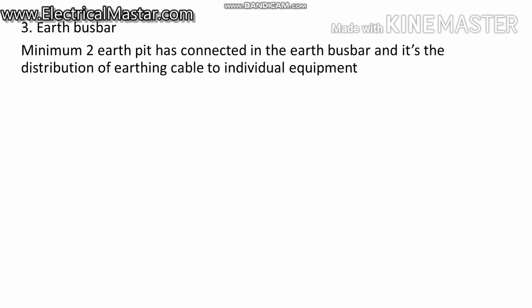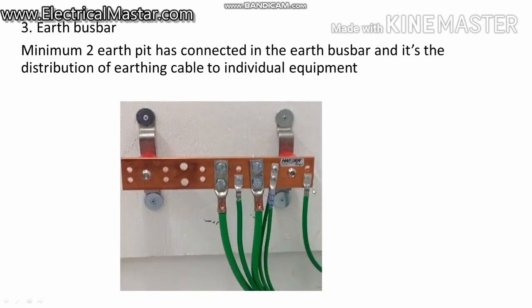And third, the earth bus bar. We can say the earth bus bar is the hub of the earthing connection. From the earth pit we give the input cable to this earth bus bar. This earth bus bar acts like a DB, a distribution board, an earthing distribution board. From this earth bus bar we take the output to the individual equipment. See here, these are the individual cables and two big size earthing connections. They are the incomers of the earth bus bar. As per the standard, you have to provide a minimum of two incomers, two earth pit connection inputs to this earth bus bar. And the output is based on the number of holes present in the bus bar. You can take as many as possible.